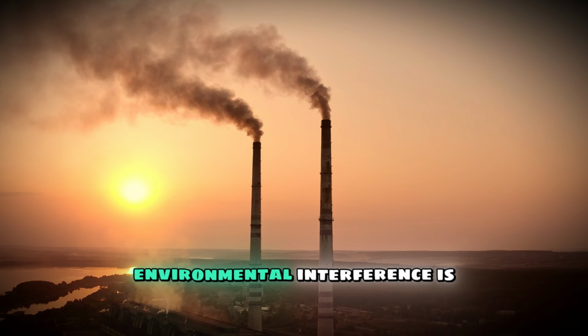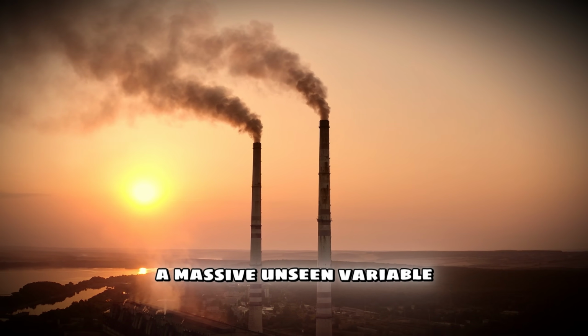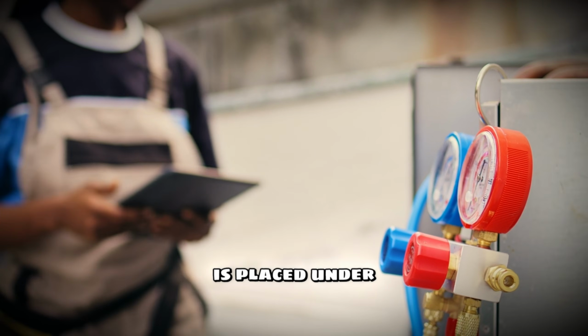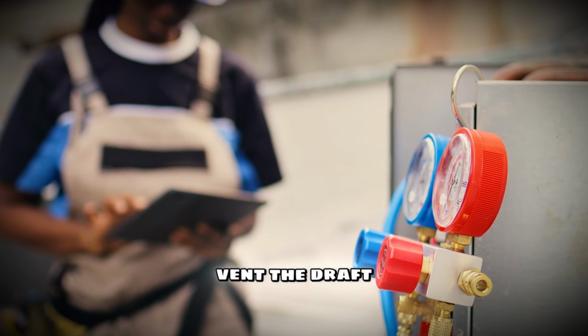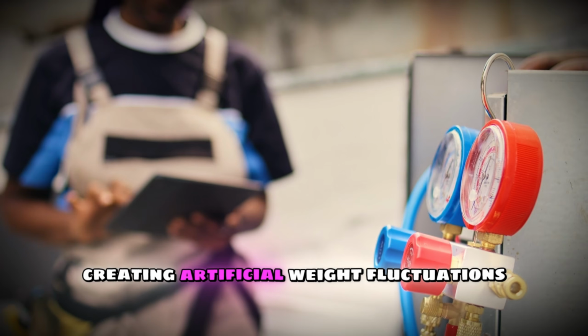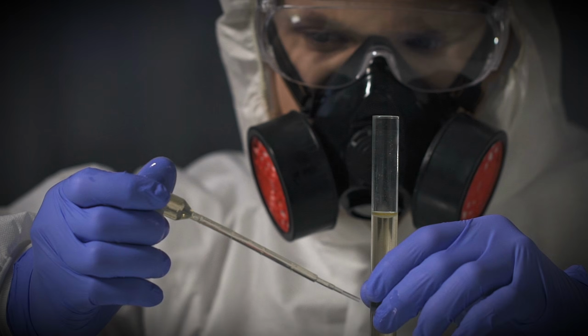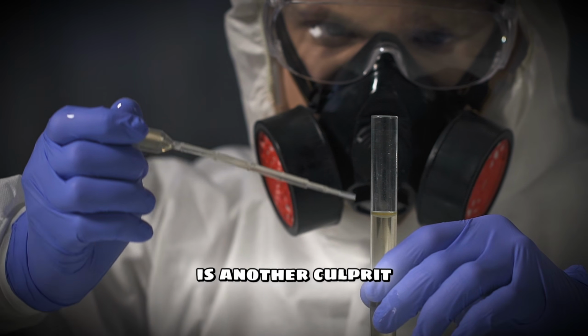Furthermore, environmental interference is a massive unseen variable. If your analyzer is placed under an air conditioning vent, the draft can push down on the weighing pan, creating artificial weight fluctuations. Improper sample preparation is another culprit.